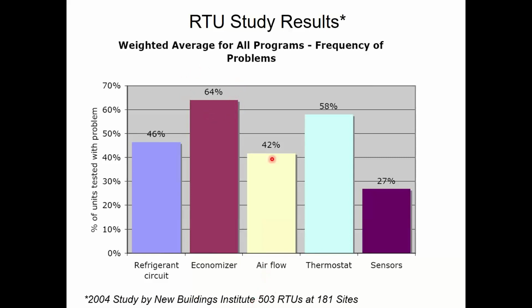42% of the time the system had too little or too much airflow. That's basically half. 58% of the time the thermostat was either wired wrong or configured wrong or not programmed. And only 27% of the time, that sounds bad, right? Where the sensors actually messed up. We always blame the sensors. Oh, maybe you got a bad sensor. It's probably one of these human-based errors that caused the problem, not the sensor drifting out of calibration.